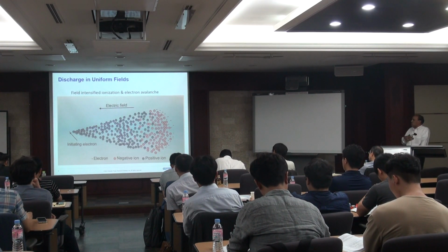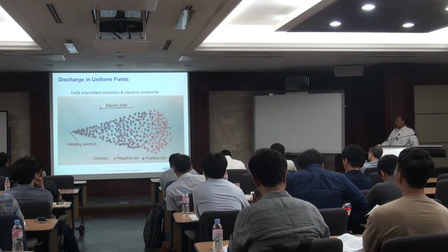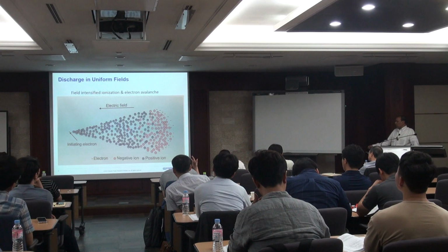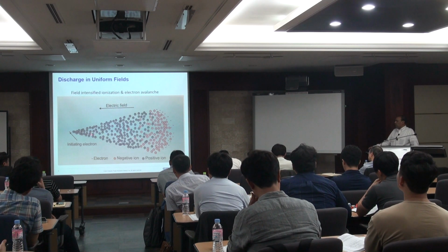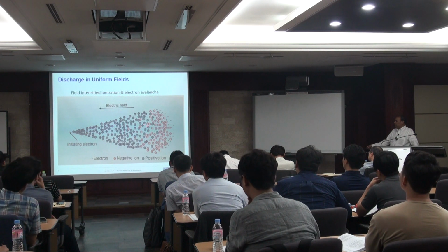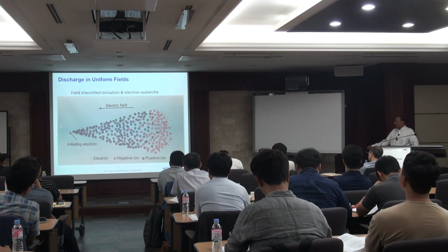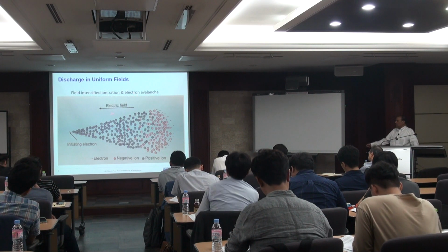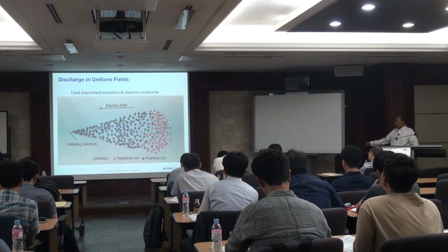Now, once you understand this, now the discharge. You have a conductor here. An electron comes out of the conductor because of corona. Say this is your ground plane here. In the air you have dust particles and a lot of things going on. So this initiating electron will start what is called the avalanche effect. It will charge the particles either positive or negative, or some more electrons could be generated. So one electron initiating from the conductor, close to the conductor because of corona discharge, might start an ionization process which is an avalanche. Avalanche means multiplying, one to many positive and negative ions, and also electrons.